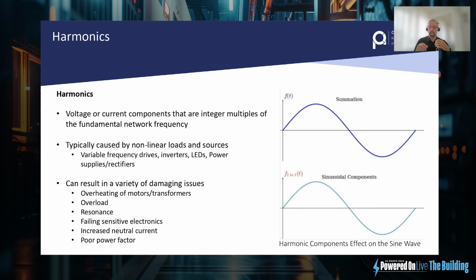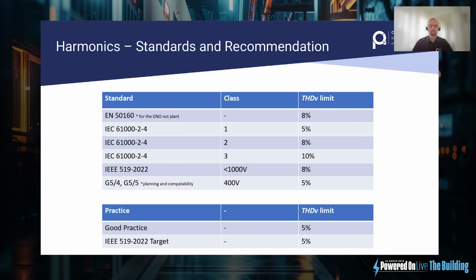And the way to do that is with mitigating that by design. Because if you don't, things like cables will overheat. Harmonics travel down the outside of the cable. It's something called the skin effect, not down the center. So if the cables aren't derated and sized proportionately for the type of harmonic load that's been connected, which in fairness to most Sparkies and installation companies, they will have no idea that this is something they need to do, then ultimately the cable can overheat over time and catch fire, burn out, all those kind of things. Other things can occur as well. You have things like resonances and other bits and pieces. So again, we can talk about that another day.